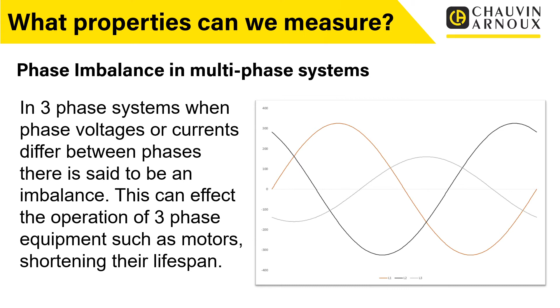And what that means is that if you are then using them with three-phase loads, like a three-phase motor, for example, then it's not seeing equal energy across all of that rotation, across all of the operation, and that again can affect the life of the motors. It can affect bearings, it can affect all sorts of things. So loading and load imbalance is something that we would be looking for when we're carrying out power quality assessments, and it's something that is very, very common. In fact, I would say it's in most three-phase installations to a certain degree. It may be below the tolerance of what would be a problem, but it is something that happens quite a bit. There is generally some sort of difference in loading across the phases, and in extreme cases, obviously, that can cause a problem.